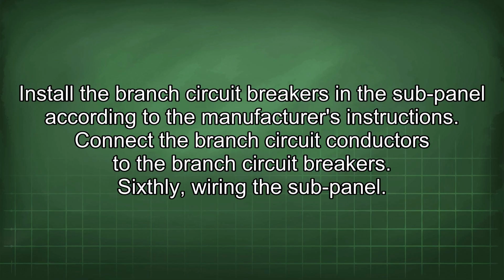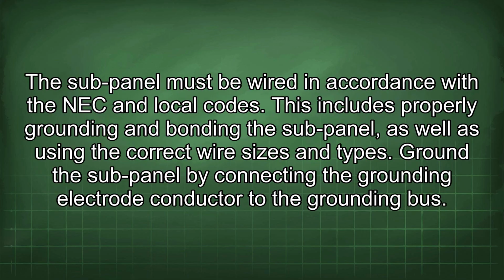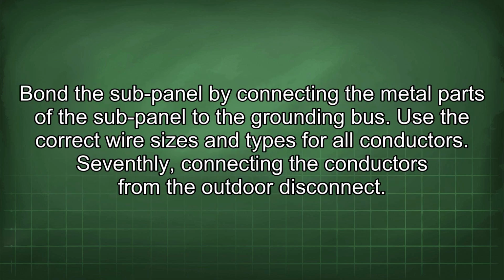Sixthly, wiring the sub-panel. The sub-panel must be wired in accordance with the NEC and local codes. This includes properly grounding and bonding the sub-panel, as well as using the correct wire sizes and types. Ground the sub-panel by connecting the grounding electrode conductor to the grounding bus. Bond the sub-panel by connecting the metal parts of the sub-panel to the grounding bus. Use the correct wire sizes and types for all conductors.